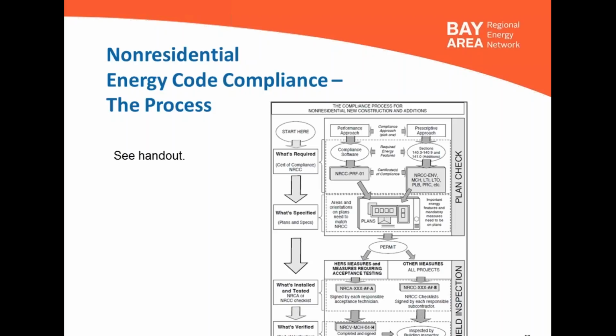They had a brand new city hall, just built under, I believe, the 2008 code. They said when they first moved into the building, it had all these fancy occupancy sensors. When they walked into a room, all the lights would shut off, and when they walked out, the lights would come on and the ventilation would start.